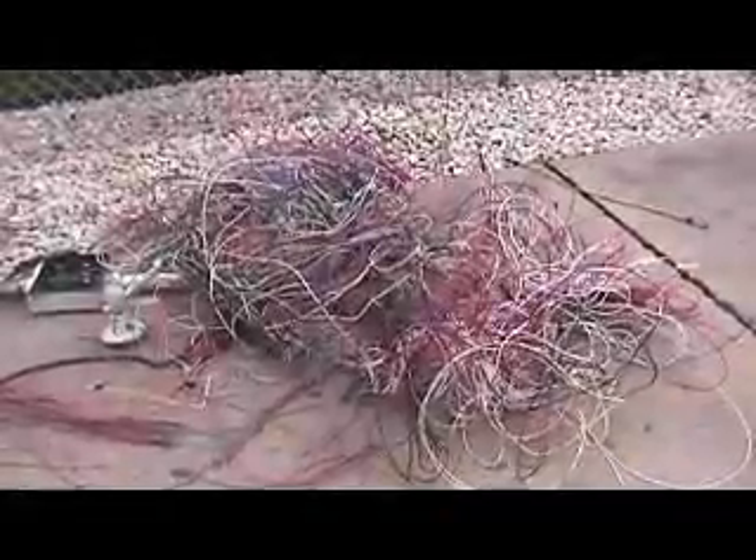Some of the fixtures, when we opened them up, the insulation actually fell off. It looked like there had been some work over the years by this homeowner or maybe the previous homeowner where things were added, and some of the terminations weren't really up to snuff. The house was completely wired in steel metal raceway — EMT — which was really conducive to replacing all the wiring. You can see the pile of TW that's pulled out here; some of the discolored wiring is evident. It was all replaced with THWN.